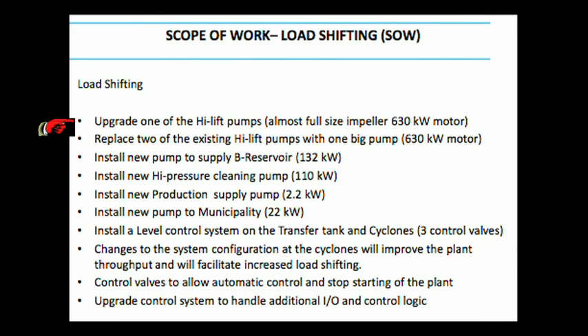So what was the scope of work for load shifting? We upgraded one of the high lift pumps to almost a full-size impeller, and put a 630 kilowatt motor on it. We replaced two of the existing high lift pumps with one big pump, as I said. We installed a new pump to supply the B reservoir, a 132 kilowatt pump, a new high pressure cleaning pump, 110 kilowatts, and a new production supply pump, that was the small little one, 2.2 kilowatts, but it was critical to the functioning of the whole project.